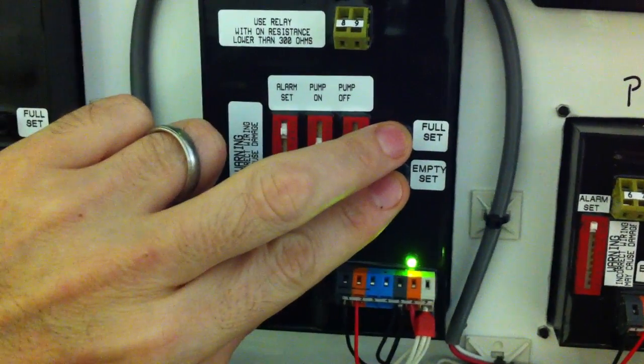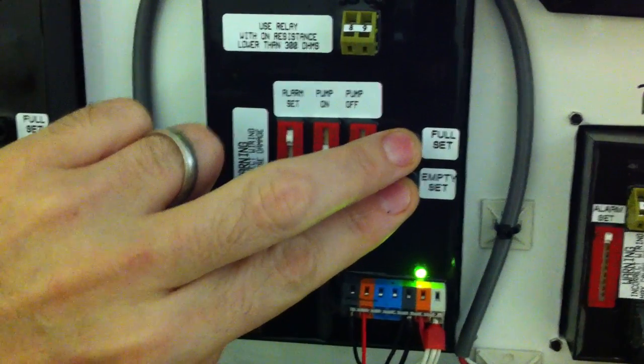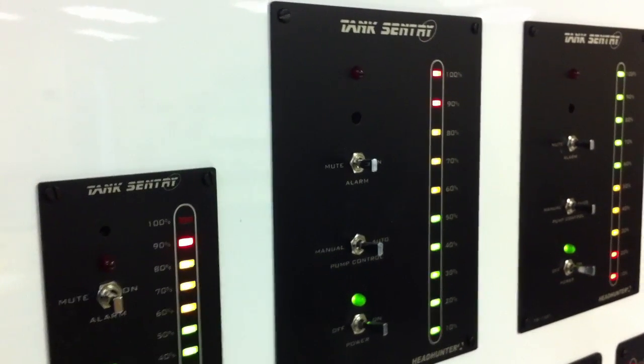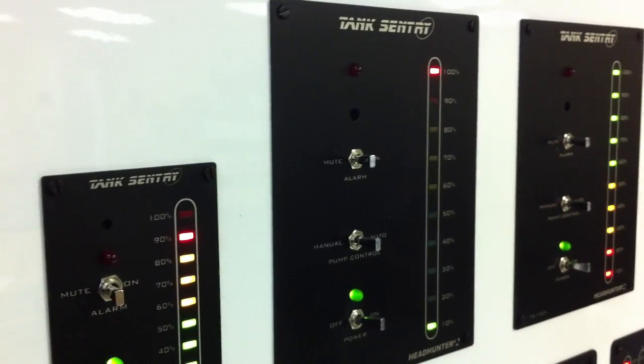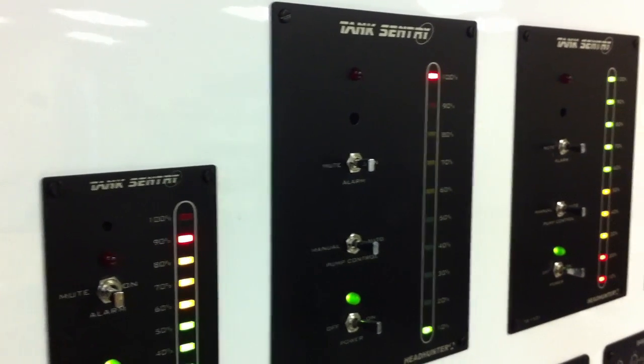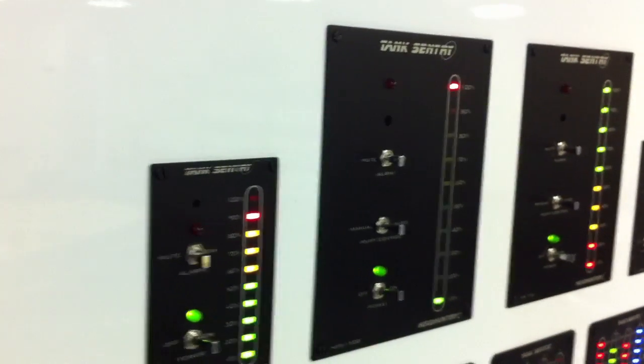To begin calibration, simply hold the full set and empty set buttons down until you get flashing LEDs on the front of the panel. Once released, the 100% and 10% LEDs are illuminated on the front of the panel. The full and empty calibration can begin.